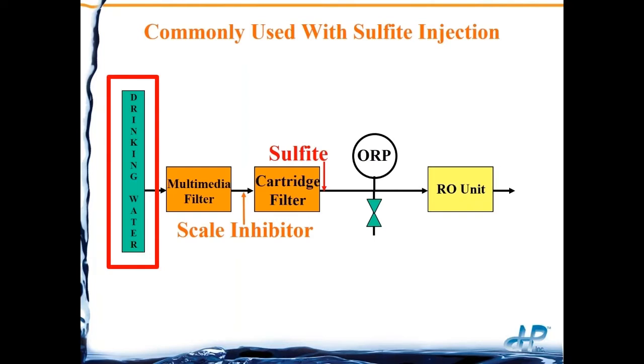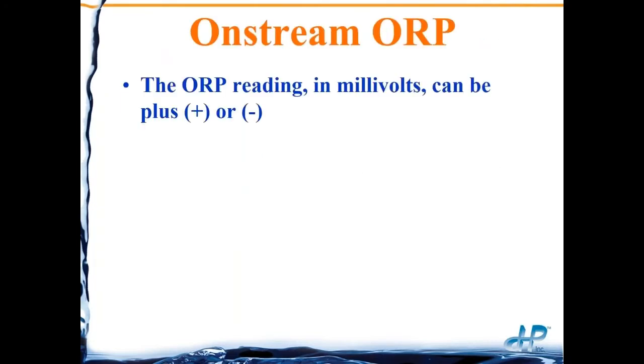As an on-stream instrument to make sure we are completely de-chlorinated, we can put an ORP meter downstream of the sulfite injection, with feedback to the sulfite injection pump. If the ORP is getting a little high, the feedback tells the pump to inject more sulfite. Typically there's also a shutdown of the RO unit — an alarm gives you a few minutes to investigate, and if the system is still in alarm, the RO unit actually shuts down to protect the membrane.